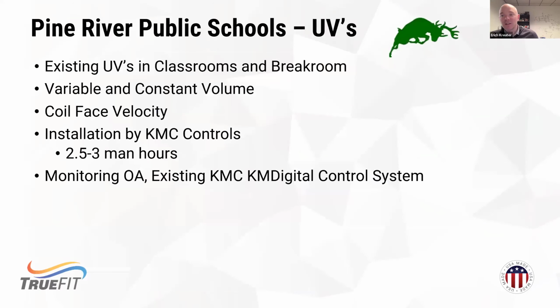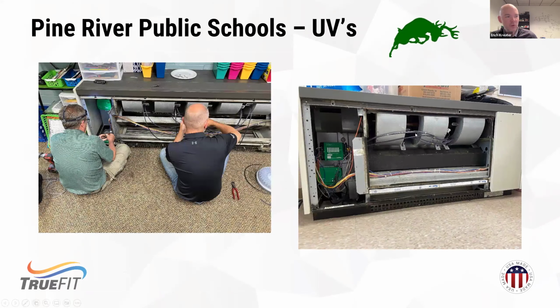The next study, or next building I'll show you, was Pine River Schools. This was a bunch of unit ventilators in northern Michigan. And you'll see here there was a 400 CFM UV and a 600 CFM UV. Same pieces and parts that go into a rooftop. We're going to go into that unit ventilator, but I don't know of any other technology that can accurately measure the airflow in that unit ventilator.